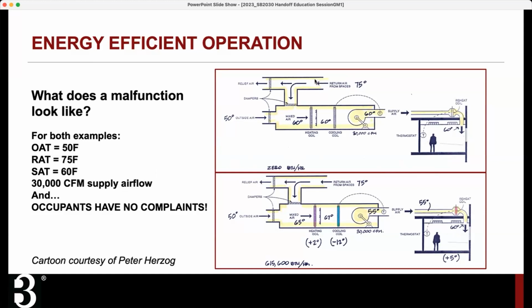But in the upper case, you'll see that the space is calling for 60-degree air to be delivered to make the thermostat happy, to meet the set point. So we're bringing back 75-degree air. The economizer is functioning correctly, so it's mixing the 50-degree outdoor air with the 75-degree return air and achieving a 60-degree mixed air temperature, which then goes through the deactivated heating and cooling coils, through the fan, through the ductwork, and is delivered to the space at the appropriate 60 degrees.